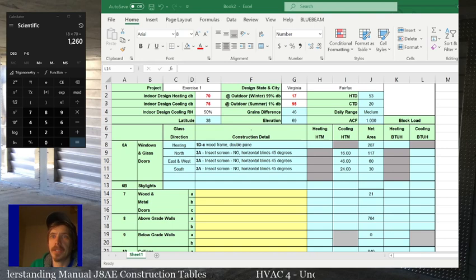Okay, so opaque panels, the heating HTM. This gets kind of complicated, but for the most part, it's the same as a 2A window. The only reason they say reference area is because on slabs, sometimes you use the square footage, and sometimes you use the perimeter. I've said that a bunch of times, so hopefully it's sinking in by now. That's the only reason it says reference area.